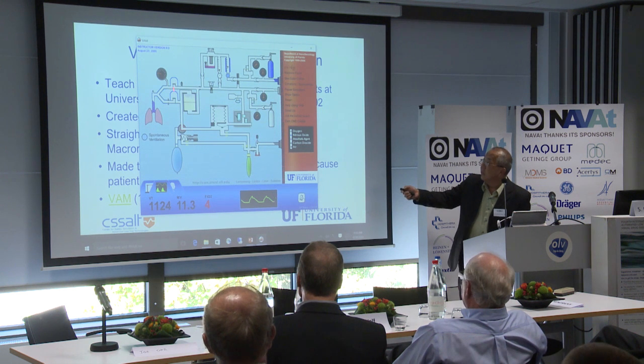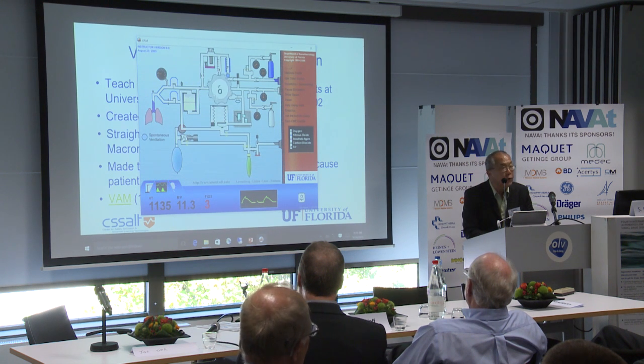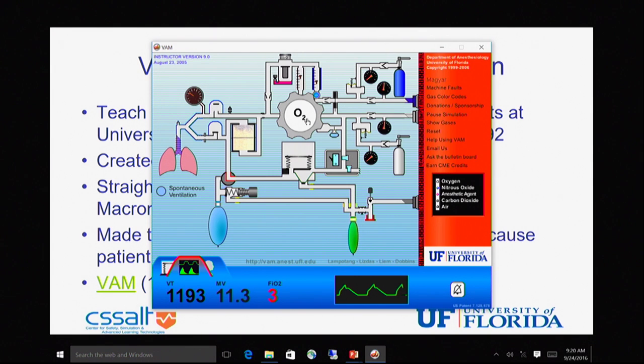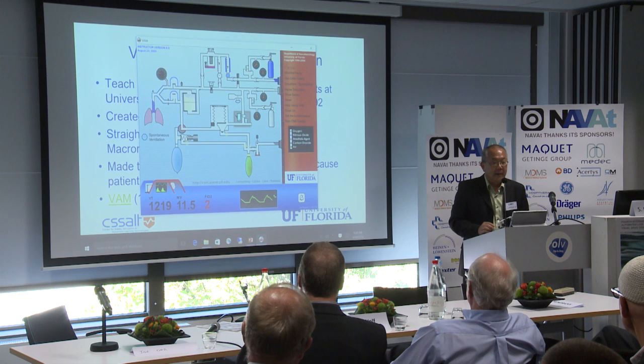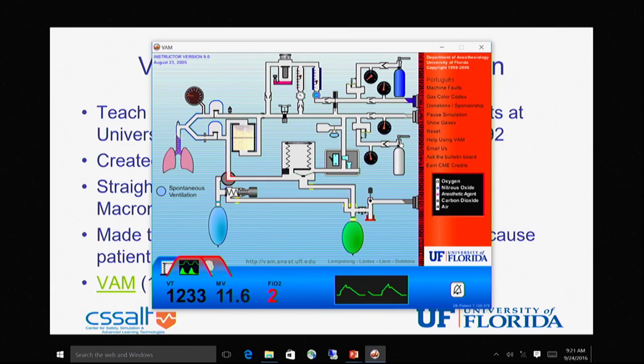Is it a stuck valve? I don't think so — if you look here, my valve is working with the bellows. Your oxygen is now down to zero. Oh, I can turn it up — I was doing low flow. Everybody was talking about low flow, so I made sure it was low flow. There's no oxygen in the pipeline — it's a pipeline issue. Someone says to disconnect from the wall. There is gas in the pipeline but it's not oxygen.